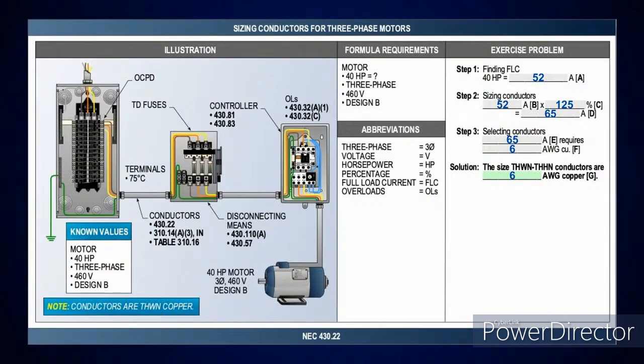Same here. Like I said, this is a three phase. It's 40 horsepower, three phase, 460 volt, design B. In that case, we'll be in table 430.250. You pick up the 460 volt, come down, match it up with your 40 horsepower, and it tells you it's good for 52 amps. You've got a single motor, 430.24 or 22, so take it at 125%. That gives you 65 amps. Go to table 310.16, 75 degrees C column, and number 6 is good for 65 amps. Pretty simple. It's the same concept. I didn't change anything. It just depends what table you're using at that point. For single phase, table 430.248; for three phase, table 430.250.